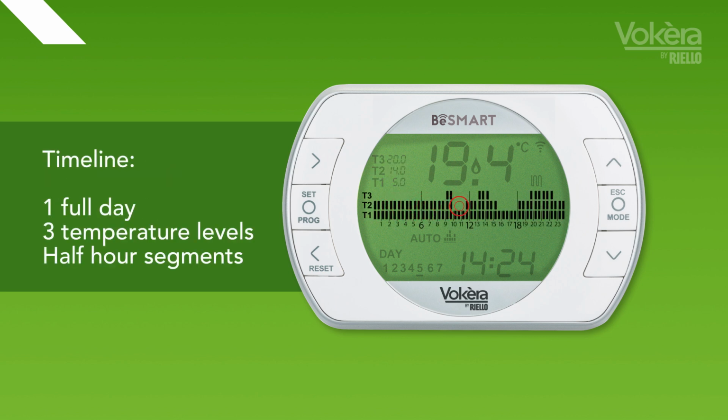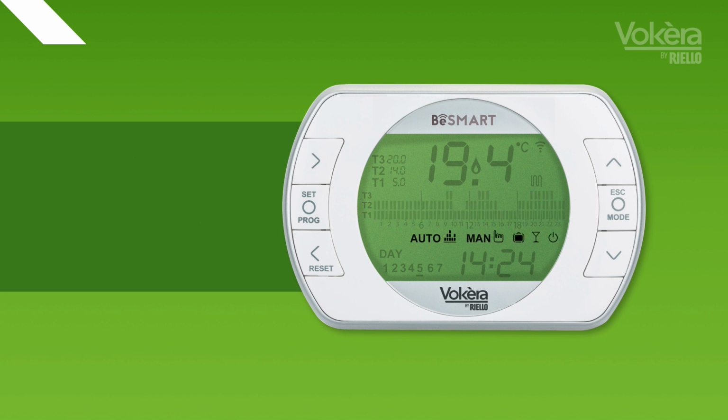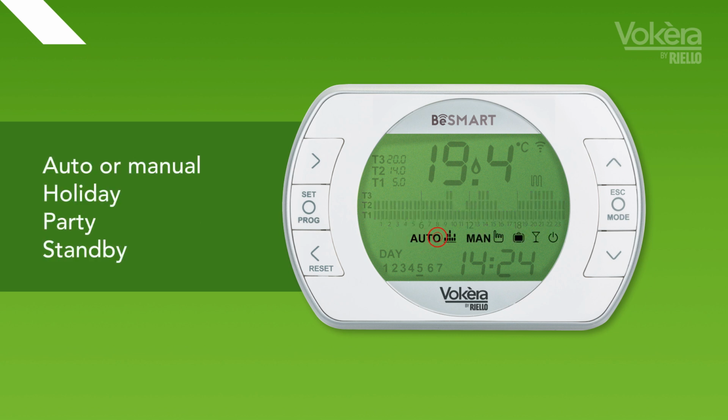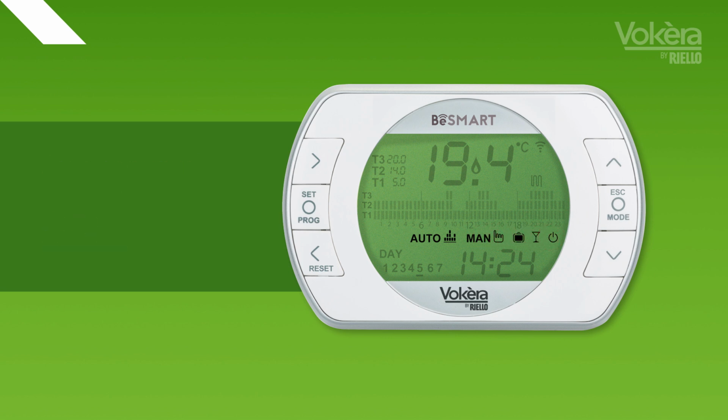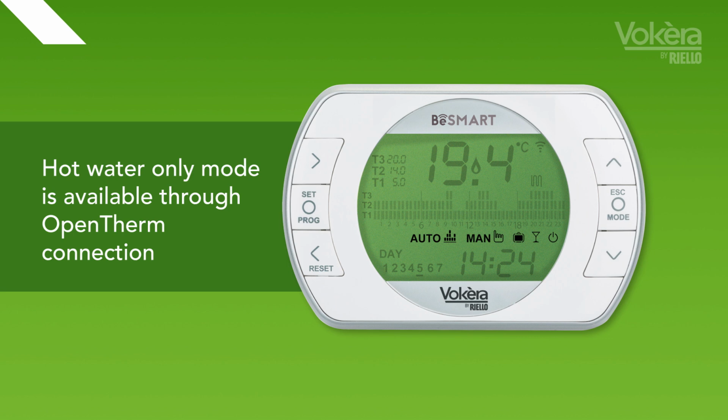Immediately below is the timeline displaying a full day in half-hour segments. As I've mentioned, each half-hour segment can have a different temperature level assigned to it. Immediately below this we have mode selection, allowing you to choose between auto, manual, holiday, party and standby modes. There is a hot water only mode available if the BeSMART is connected to the boiler by the OpenTherm protocol.